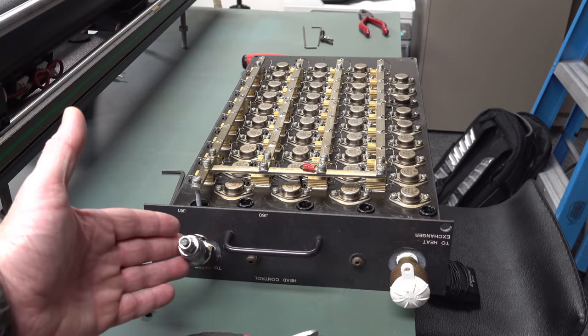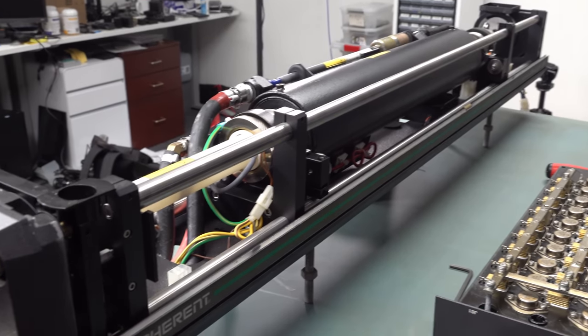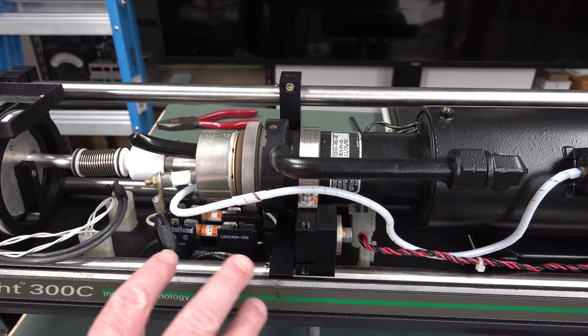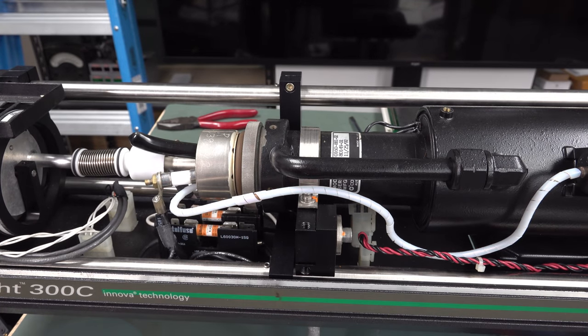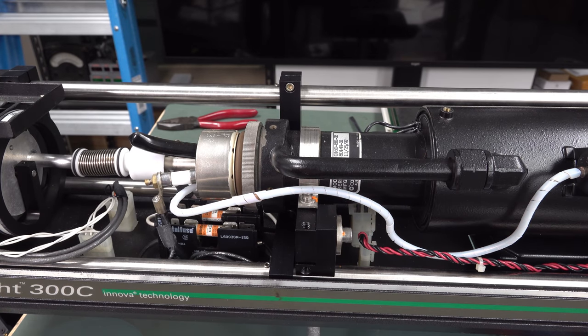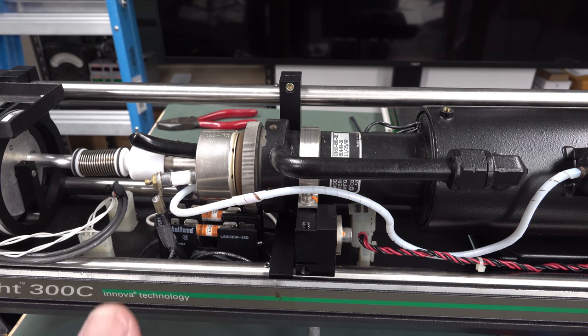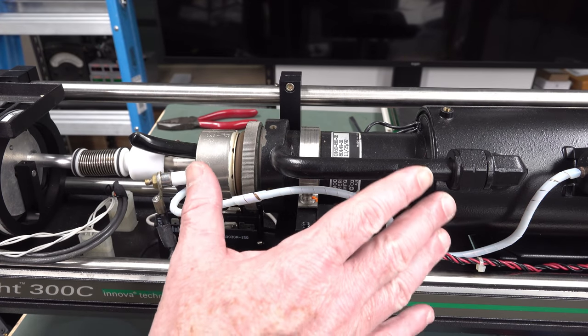Then it pumps it into here, and then it goes into, like, I'll call that the inner casing, I guess. So it actually goes into this outer ring, and that's where that temperature sensor there is. So the water flows into here, into the inner casing, and then it'll flow all the way through the inner casing. I would guess. And then you can see that there's another tube that comes out here like this. And this goes over to here to, I guess, the outer casing, for want of a better word. And then out here, and then back. And that goes up the cable all the way back to the power supply. And then the power supply, which we've looked at in the previous teardown, we've got the heat exchanger here to get all the heat out of the power train here right over here. So yeah, it's remarkable. And somewhere in here, there's actually a catalyst which basically absorbs any ozone produced.